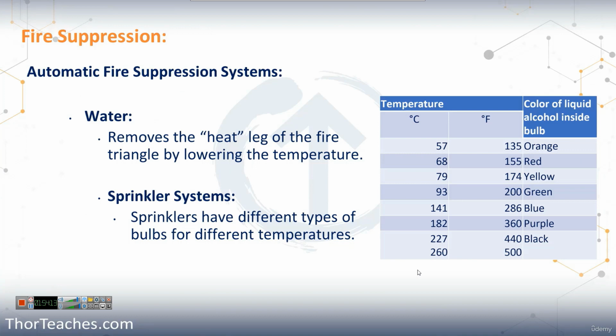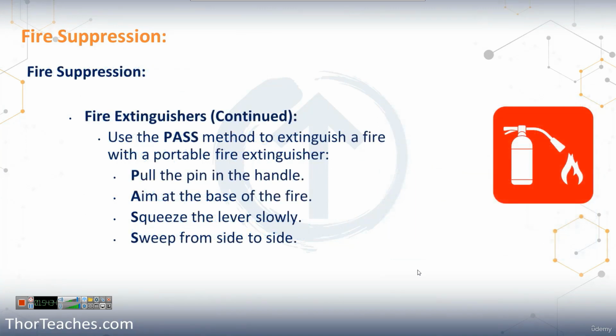In the rest of the building, not the data center, we would have wet pipe, meaning that there's water all the way up to the sprinkler head. As soon as the glass bulb in the sprinkler head breaks, water comes out. In the data center, we have dry pipe, meaning there's compressed air in the pipe and someone has to push a button to release the water. We don't want this to happen by mistake. And then when we use the fire extinguishers, we use the PASS method. We pull the pin, we aim at the base of the fire, we squeeze the handle slowly, and then we sweep from side to side.